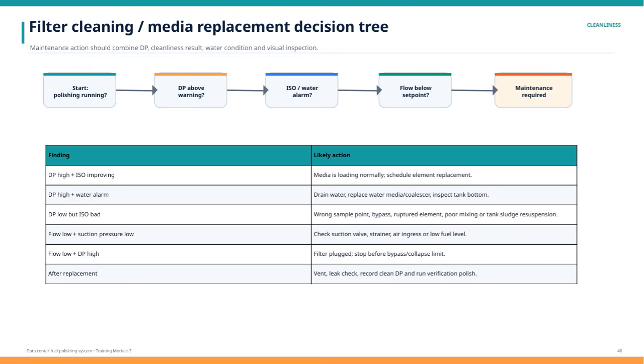For example, if the differential pressure is high, but the ISO cleanliness is improving, this usually means the media is loading normally, so schedule a replacement of the element. If the differential pressure is high and there's a water alarm, you should drain the water, replace the water media or coalescer, and inspect the tank bottom for any contamination. In cases where the differential pressure is low but the ISO cleanliness is poor, this could indicate issues like the wrong sampling point, bypassing, a ruptured element, poor mixing, or sludge resuspension in the tank.